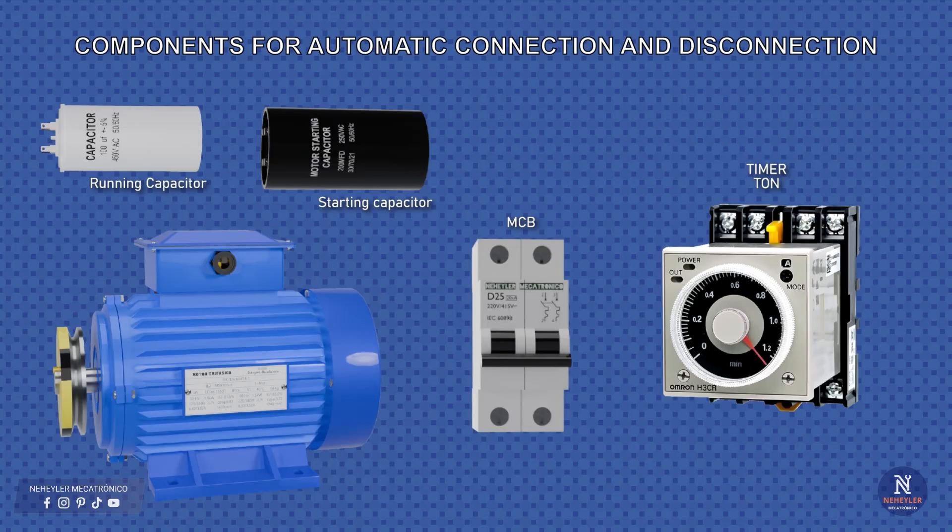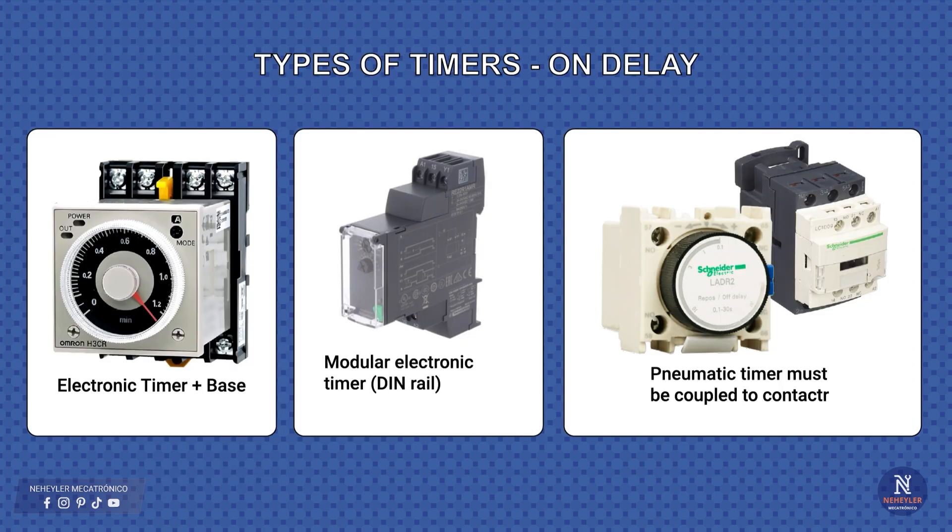Let's now move on to the automatic disconnection with a timer. Unlike the manual method we just saw, here we no longer depend on a push button, but we use a timer that automatically disconnects the start capacitor after a few seconds. In the market there are different types of timers, but for our case we are going to focus on on delay timers. On the left we see an electronic timer with a base, widely used in industry, precise and easy to install with an 8-pin socket. This is the one we are going to use in this video to disconnect the start capacitor.